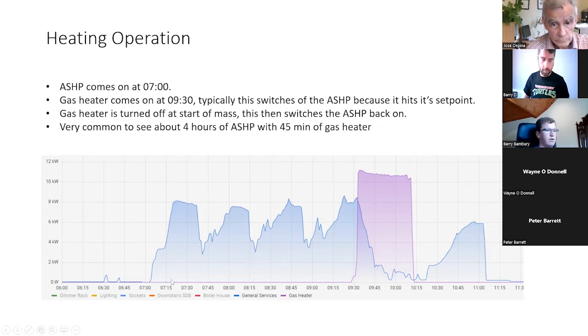It's 12 a.m. or 6 a.m. in the morning here until about lunchtime. So this is just a zoom in of the morning, and that's kilowatts consumption. This is the actual consumption of the heat pump, and this is just the fan from the gas heater. So you know what I mean? The actual electrical consumption of just the fan from the gas heater is greater than the actual consumption of the whole space heating from the air source heat pump.